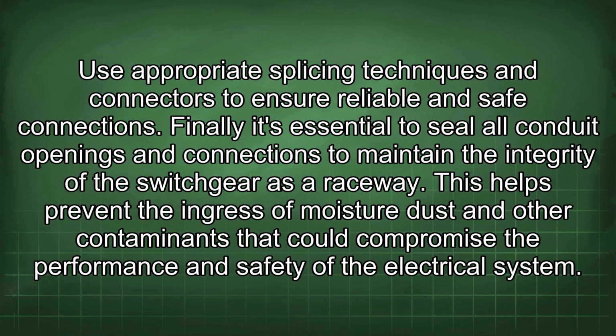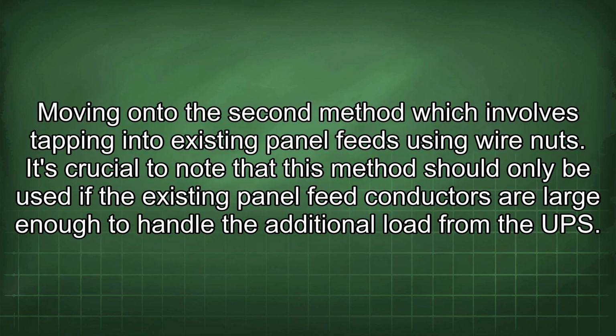Finally, it's essential to seal all conduit openings and connections to maintain the integrity of the switchgear as a raceway. This helps prevent the ingress of moisture, dust, and other contaminants that could compromise the performance and safety of the electrical system. Moving on to the second method, which involves tapping into existing panel feeds using wire nuts.